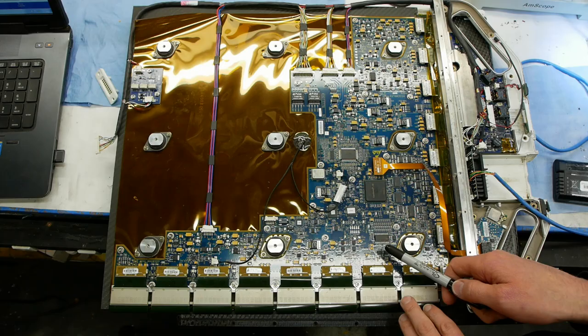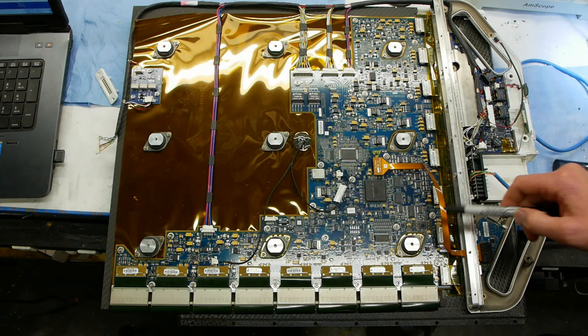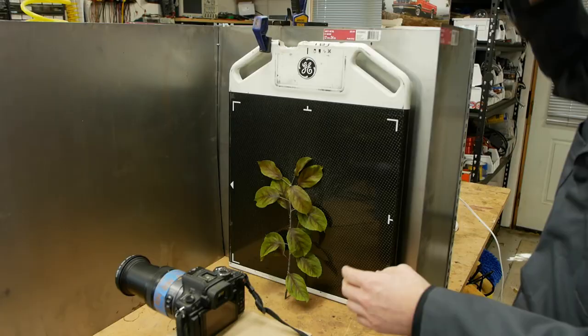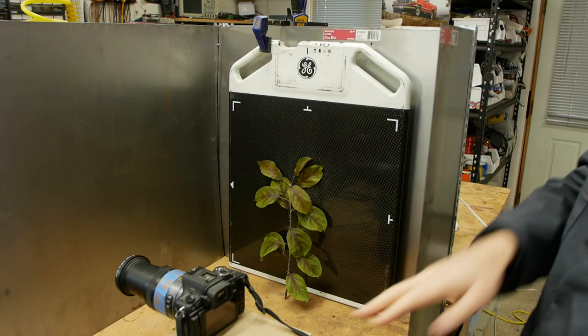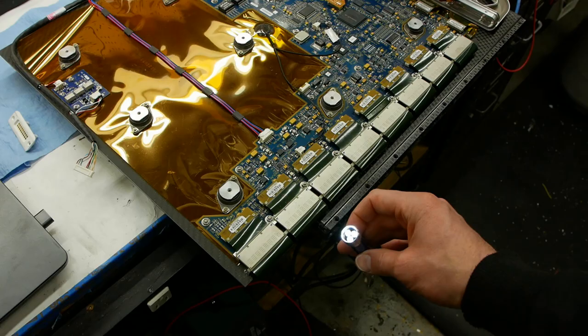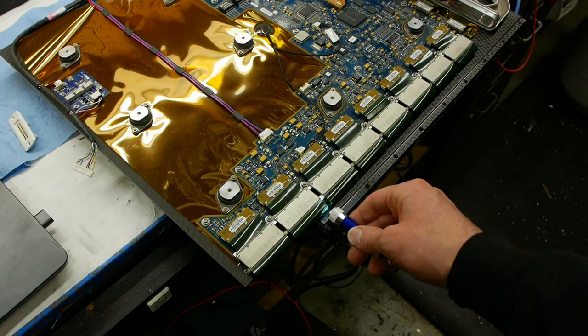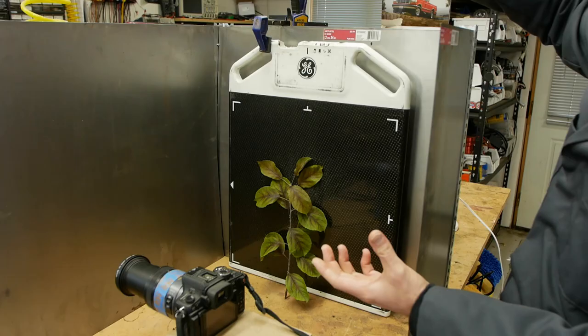It's basically a gigantic camera sensor in there. Whereas in a camera like this, the sensor is on the order of 1 or 2 centimeters squared, this is a 40 by 40 centimeter camera sensor, a 4 megapixel sensor. But the area is absolutely enormous so that it's very sensitive to light. The bigger the sensor is, the bigger the pixels, the more sensitive they are to incoming photons.